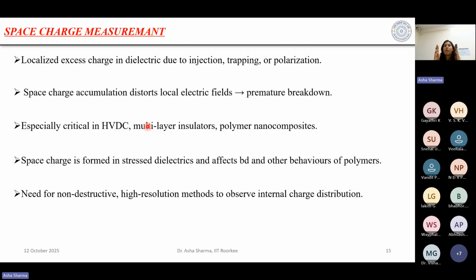But if it is HVDC, we have uniform polarity here. So there is no chance for this space charge to change its position. If it is in addition with the main field, it will ultimately cause the degradation of the insulating material. So it is very, very important to address this issue. We are also speaking a lot about whether we could transmit the power using HVDC overhead lines. There are three HVDC overhead lines, up to plus minus 800 kV, in India. We are also thinking of transferring the power with more and more HVDC transmission because of the converters, right? So if we are talking about HVDC, we can't ignore this space charge phenomenon. We have to take care of this.